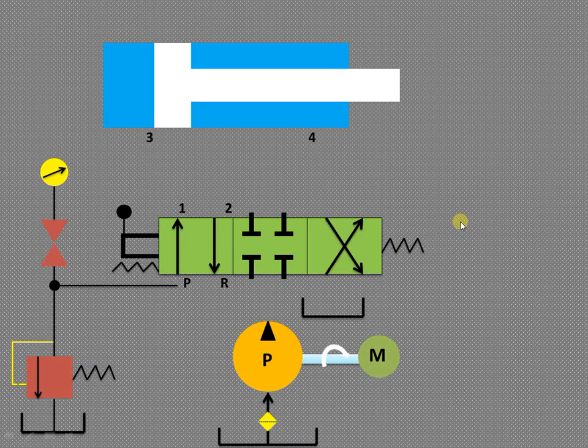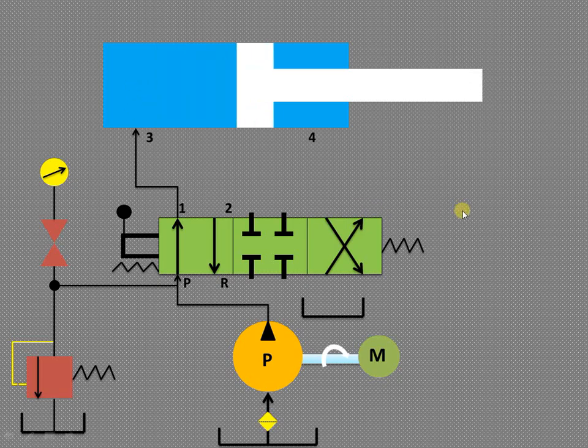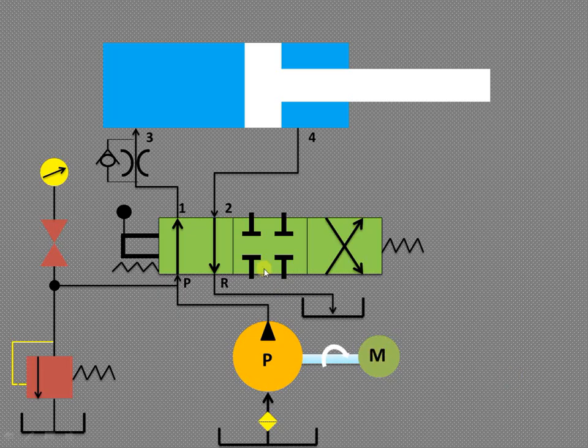Let us understand the forward motion of the piston through animation. Liquid from the reservoir is pumped by the pump, then enters port P. From port P it goes to port 1, from port 1 it enters port 3, and the fluid acts on the piston surface causing it to move in the forward direction. The liquid from the rod end enters from port 4 to port 2, and from port 2 to R — back to the reservoir.